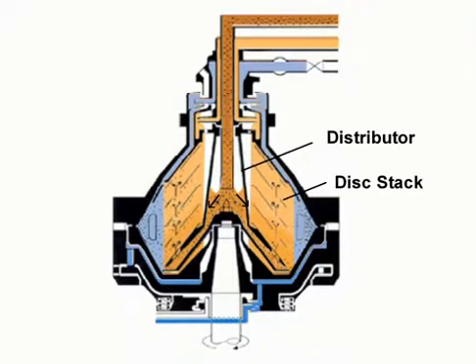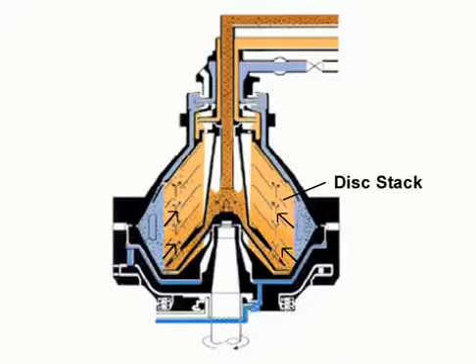When the dirty oil reaches the slots of the distributor, it rises through the channels formed by the disk stack where it is evenly distributed. Dirty oil is continuously cleaned as it travels towards the centre of the bowl.